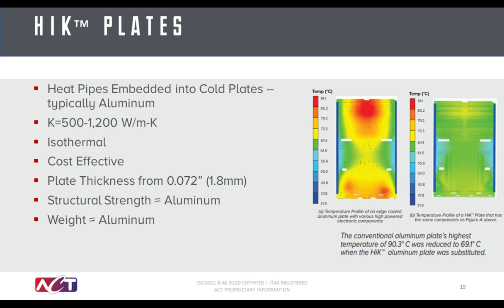Other relevant experience utilizing this high K plate technology, specifically within the cabinet cooling realm, can be mounted directly to the base of an IGBT module, for example, to better isothermalize that module. This same thermal technology can make up the structural seal and optimized thermal solution for that application, and it can move heat to the most effective cooling location, spreading throughout the fins.